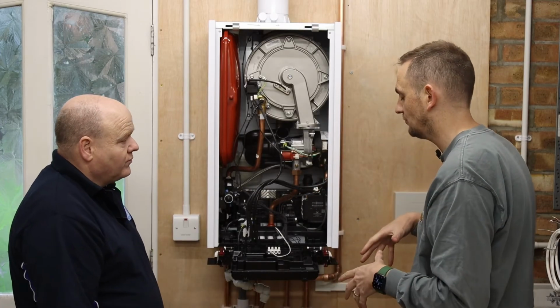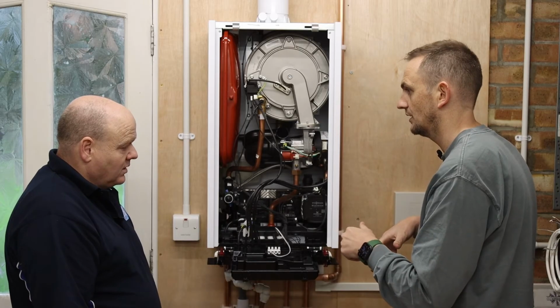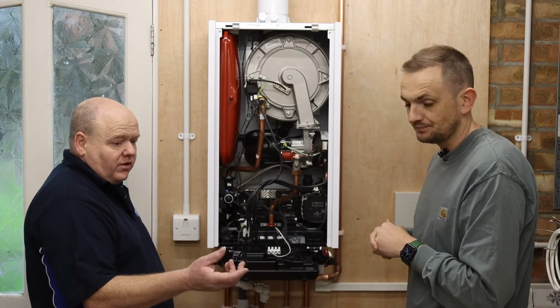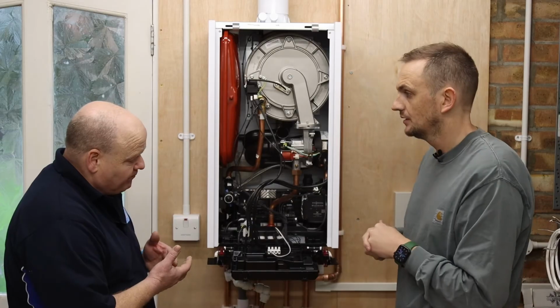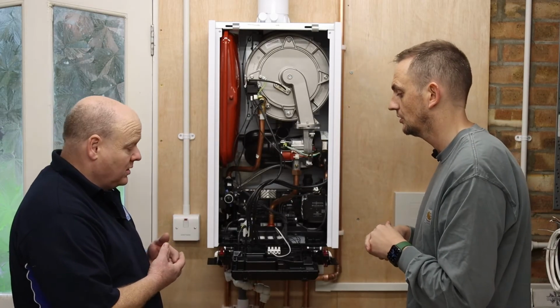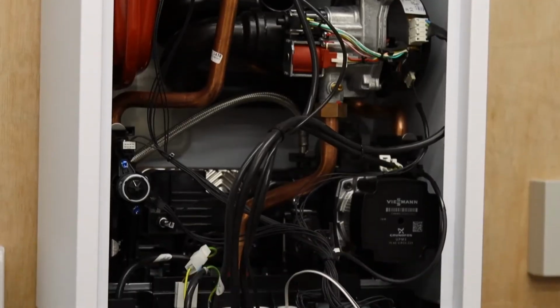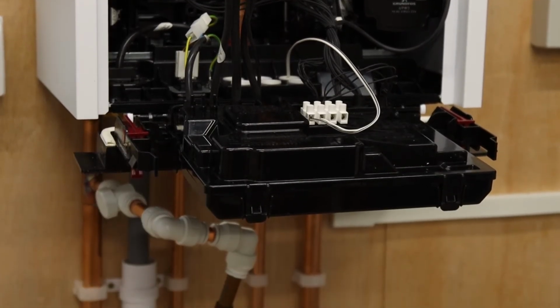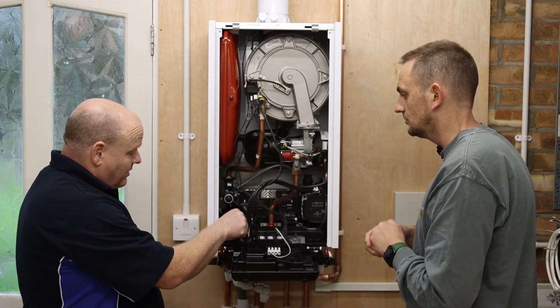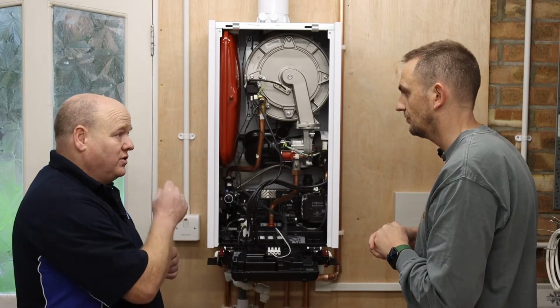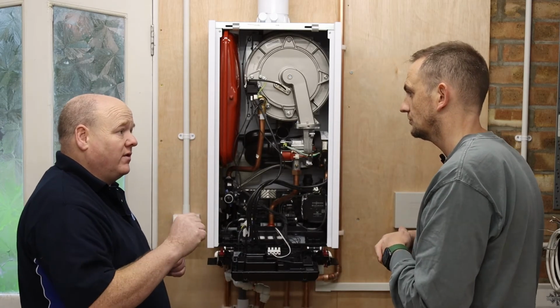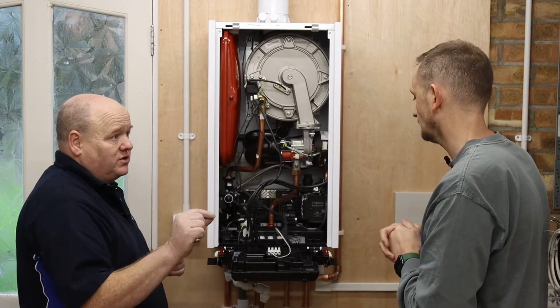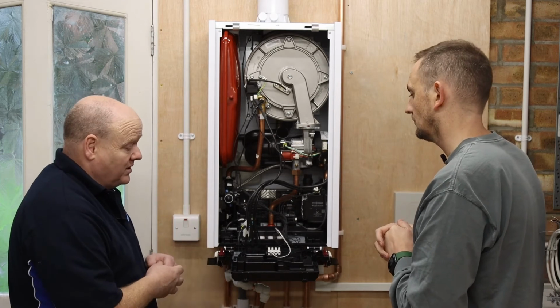How have you wired this? Have you put it into the switch live? So I've used the control, the EPH control, and wired it on OpenTherm into 1 and 2 on here. That's really easy to wire. It comes with a pre-done lead as well, so you just connect that to live, neutral and earth, and then the OpenTherm side you just do into the low voltage. So it's really simple to wire.